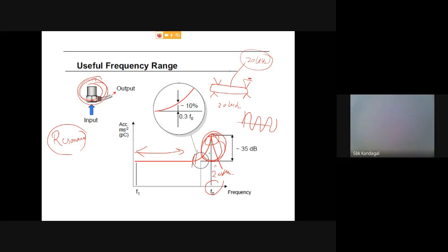That's why, whenever you are using sensors, be sure what its natural frequency is, because the natural frequency comes from the preloaded disk inside the sensor. The preloaded disk is put in the compression accelerometer to avoid chattering of the piezo crystal. And that's why you will get a DC bias.